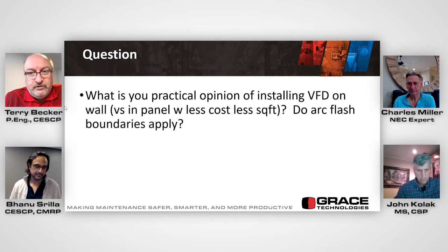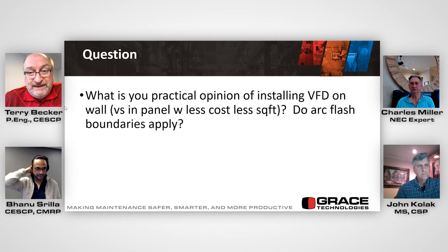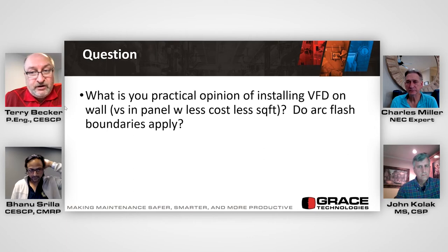So we have unqualified staff - qualified operations workers aren't qualified persons. They can't open up or take the cover off the drive, right? But they can walk up to it, they can use the HMI. They don't need arc flash or shock PPE underneath this, to do some minimum maintenance, right?